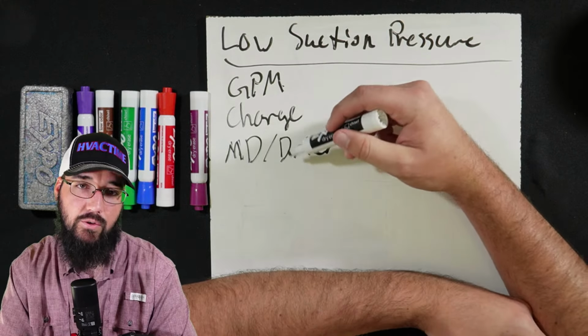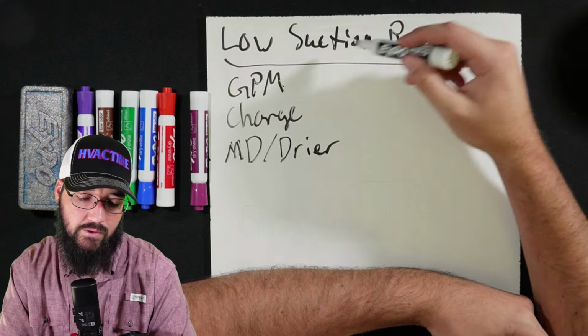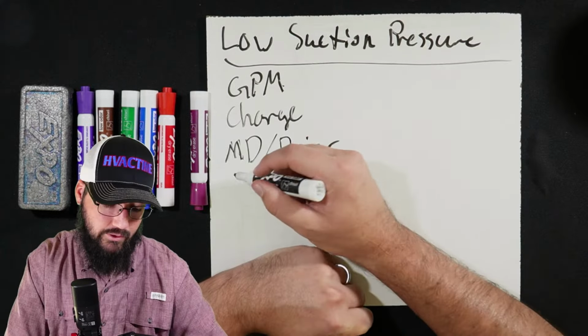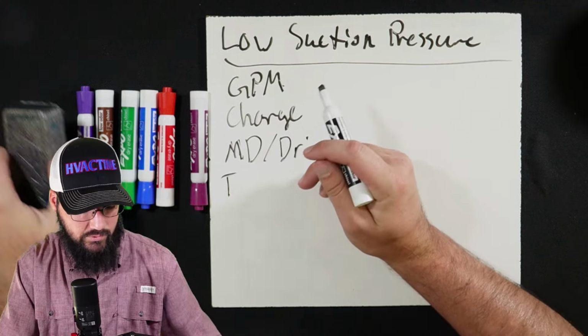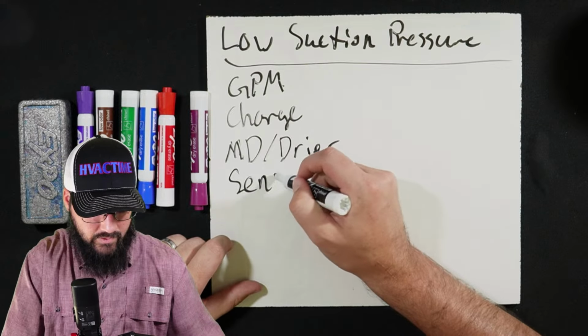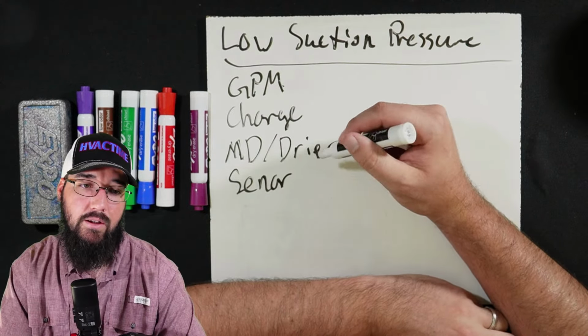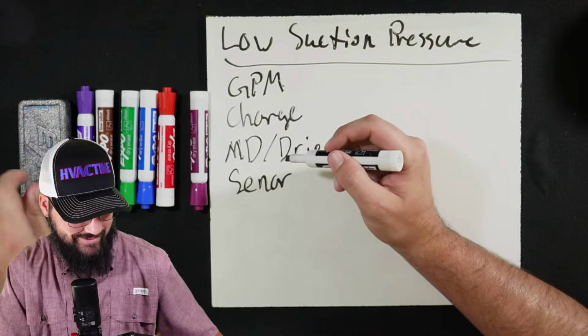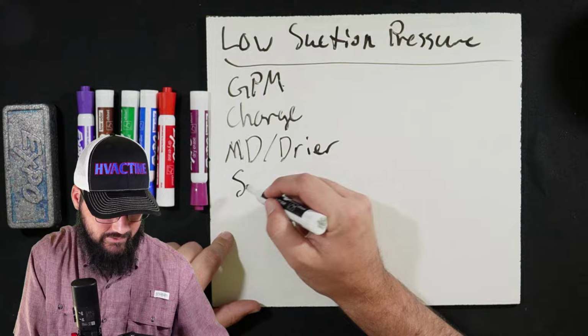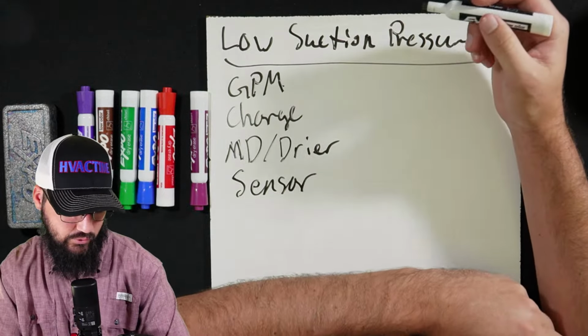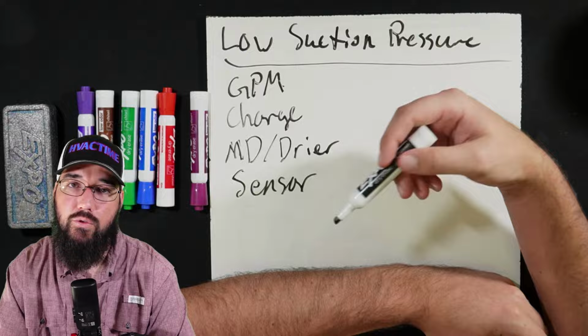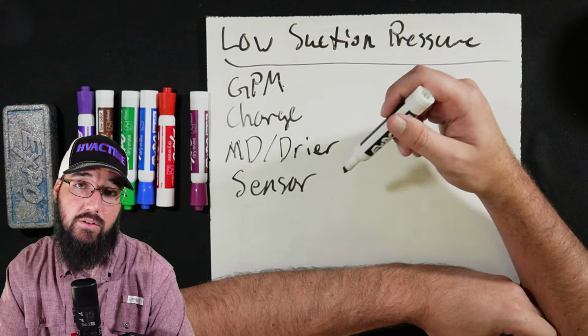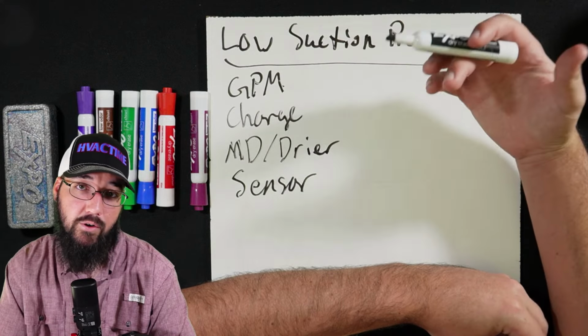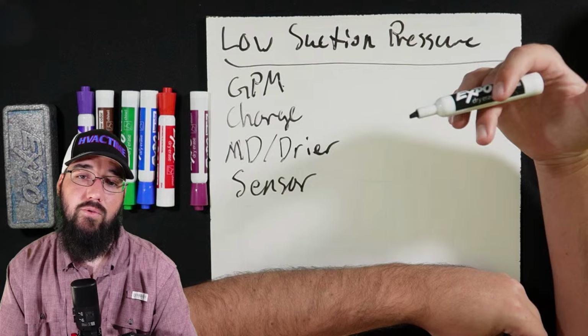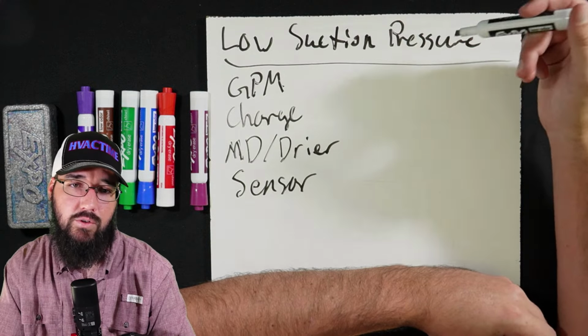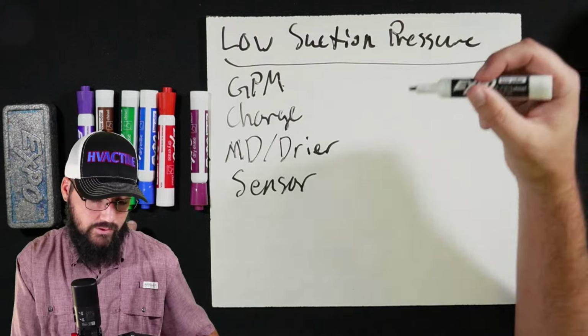Okay, and you'll see this: you'll have really good subcooling, but the suction pressure is just not jiving. It could be a transducer issue or a sensor issue. We're just going to go with sensor. If there's an issue with a transducer, temperature sensor, something like that, it could be causing it to starve the evaporator, or the evaporator may be perfectly fine and the sensor is just telling you it's got a low suction pressure when it really doesn't. So that could be a transducer issue at that point.